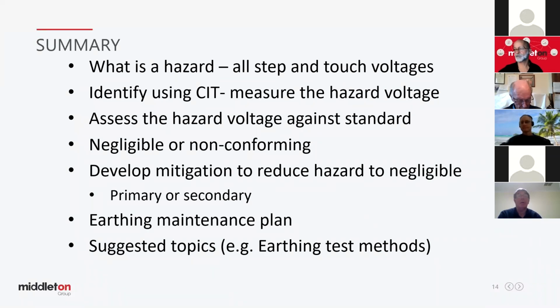So as time's getting on, we're nearly on the half hour, so we'll allow time for some questions. But basically, just in summary, what is a hazard? Well, all voltages are hazards, as we've seen, but we do classify them as complying and non-complying, as we've discussed. We identify them using a current injection test. We can measure the hazardous voltage using that method. We can assess the hazardous voltage against the standard, work out whether the hazard is negligible or it's non-conforming. If it is, we've got some more work to do. And that work will be to develop some mitigation to reduce the hazards to negligible, using primary or secondary mitigation methods. We should also include, for the lifetime of the asset, an earthing maintenance plan as well.